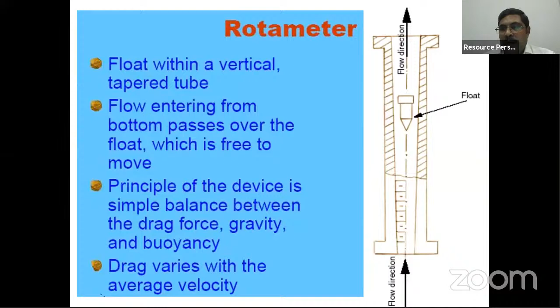Here in the rotameter, you see the flow area is tapered to have the force balance at any location. At any given flow rate, the float finds its position with respect to the flow rate. For a given position, the net upward force acting on the float will be equal to the net downward force. The float will be designed for one particular liquid. A float which is designed for air cannot be used for water or some other application. You cannot use it. Similarly, there is one important thing here: the ratio of the density of the float to the density of the flowing liquid.